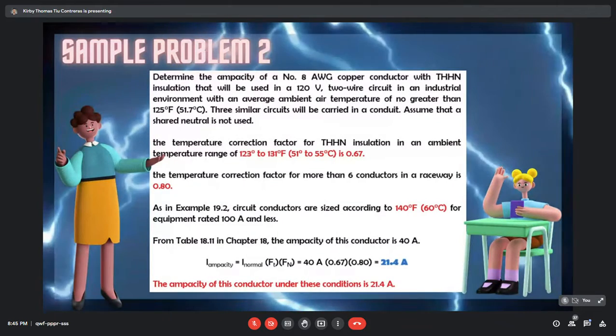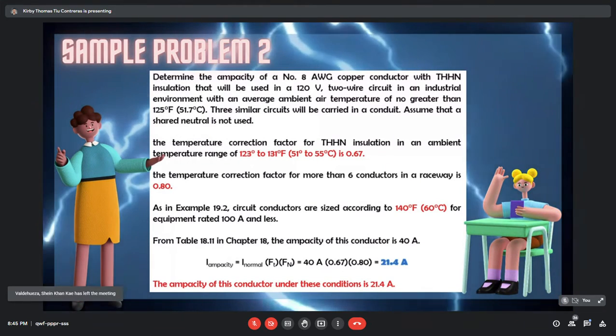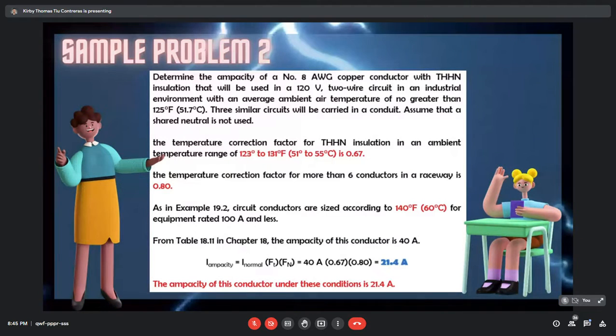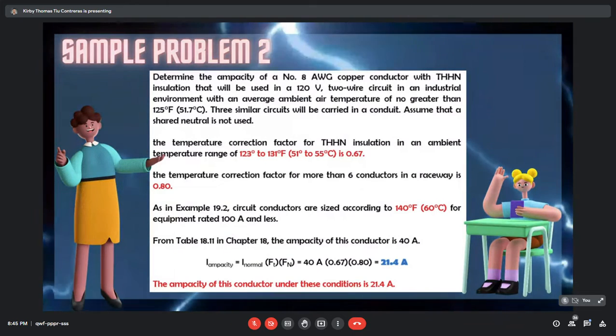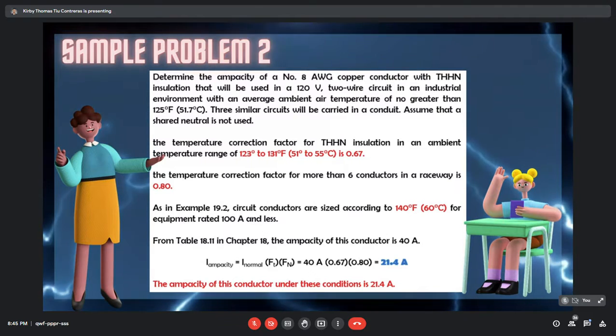So next example, determine the ampacity of a number 8 AWG copper conductor with THHN insulation that will be used in a 120 volts two-wire circuit in an industrial environment with an average ambient air temperature of no greater than 125 Fahrenheit or 51.7 degrees Celsius. 3 similar circuits will be carried in a conduit. Assume that a shared neutral is not used. The temperature correction factor for THHN insulation in an ambient temperature range of 123 to 131 degrees Fahrenheit is 0.67.